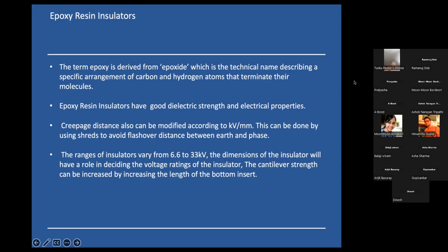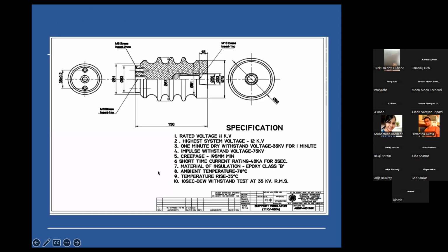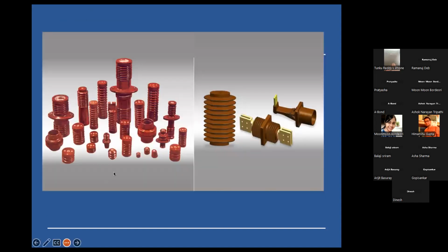Another important aspect is the cantilever strength. The strength of the insulator is a very important factor, and it can be increased by increasing the length of the bottom insert. Next slide. It's just a basic cross-sectional diagram of our epoxy insulator. It has a few technical specifications like creepage, material, and ambient temperature rise, and this is basically an 11 kV insulator. It's just a small picture of our range. One is a CAD drawing of our epoxy insulator, and another shows the various sizes, from 6.6 kV to 33 kV.